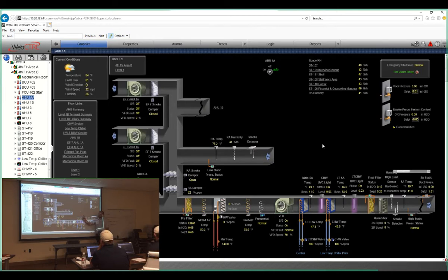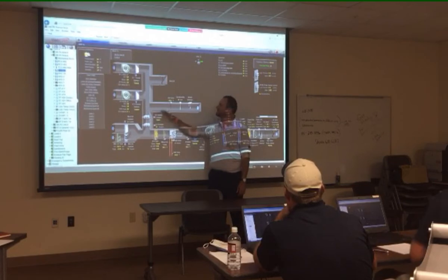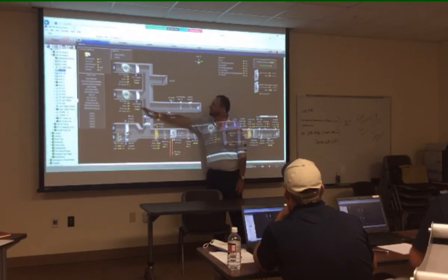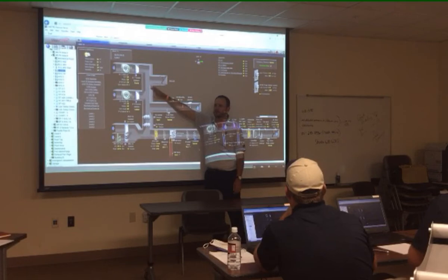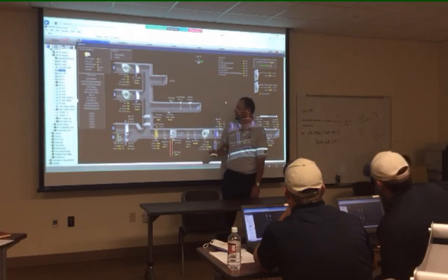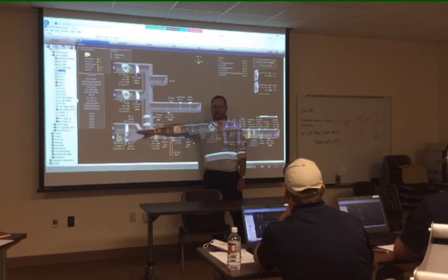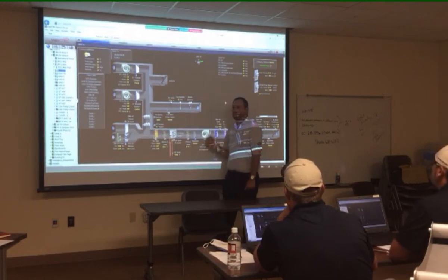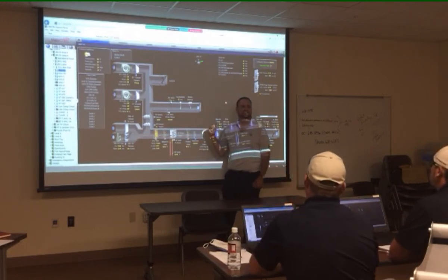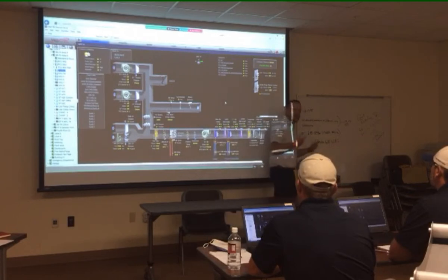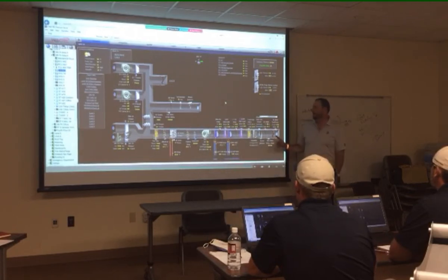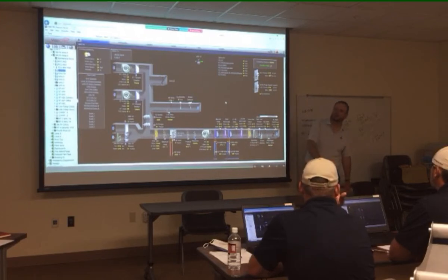Kind of walk through the sequence of the dampers closing. Yeah, so when this happens, this damper closes. These are going to start pulling the return directly from the unit. The unit's going to actually open the outside air damper and continue to put air into the space, unless we get a smoke damper or smoke detector that trips on the air handling unit. Then we shut the air handling unit down because we don't want smoke in the space.